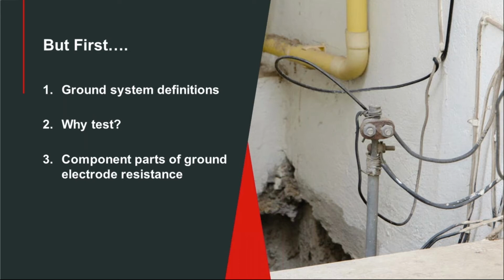So another way to address that is to go to a grounding company and get software. The companies that make your ground rods, grids, and other materials will typically provide software. You put it in a computer and tell it what you want, including the resistivity measurement you'd have to input, and what ground resistance you want, say a 5 ohm ground. Then it designs it for you, makes a schematic, and shows you that you need, for example, 20 10-foot rods, or whatever it happens to be. That's another way to address grounding your system if you're faced with that task.